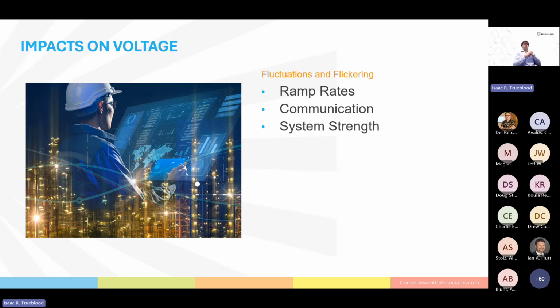While ramp rates help with the flickering and equipment wear and tear, distributed energy resources can also cause voltage fluctuations a voltage regulator at a feeder cannot detect. One way to mitigate this is to provide communication between the voltage regulators and instrument transformers close to the end of the feeder, preferably near or at the distributed energy resource. This allows for a voltage regulator to determine when the DER is decreasing its generation and raise the voltage to prevent undervoltage conditions at the end of the feeder. Inversely, it can prevent the opposite case of voltage regulators creating overvoltage conditions at the end of the feeder caused by a distributed energy resources increasing generation.